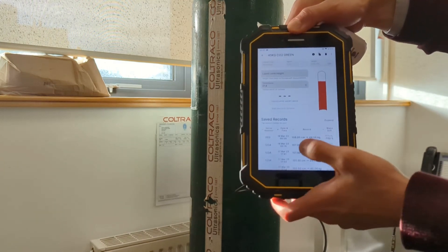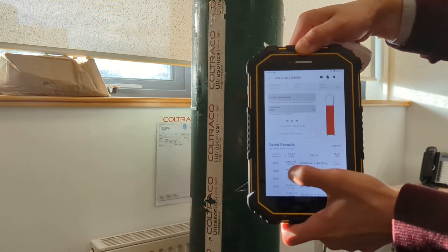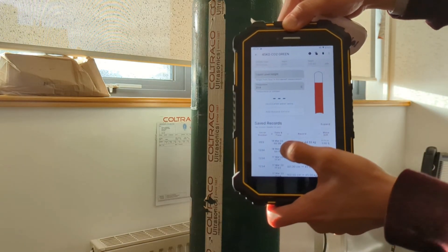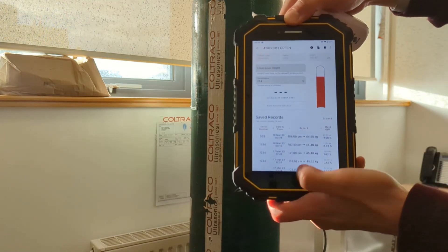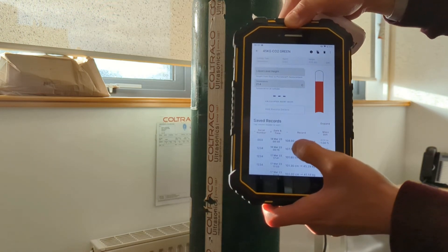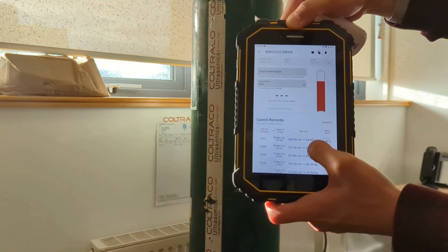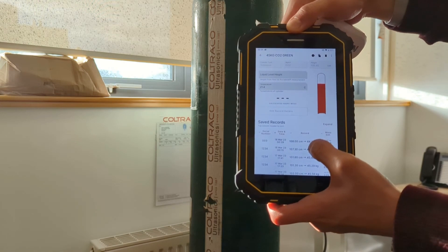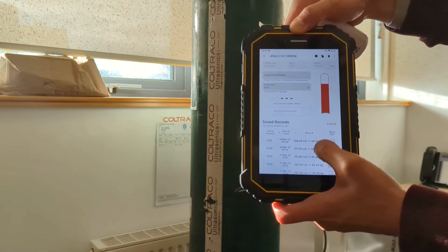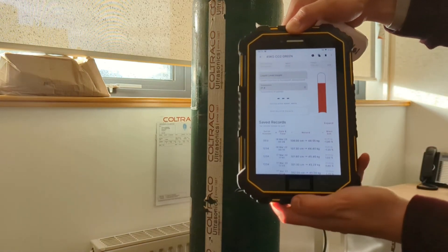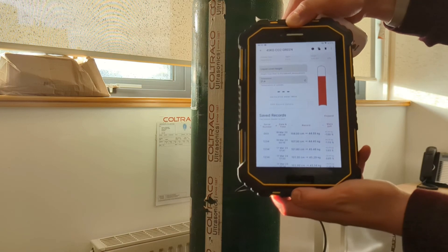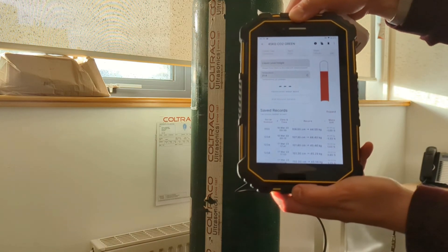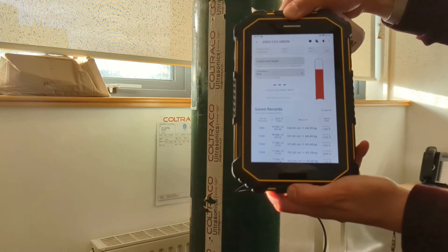And you can see that the latest record with the serial number 003, and the time and date of when it was taken, shows that at 108cm, which is what we found earlier, the record is 44.5kg of agent in this cylinder. And the difference between what I found versus what was printed on the cylinder is 1%.